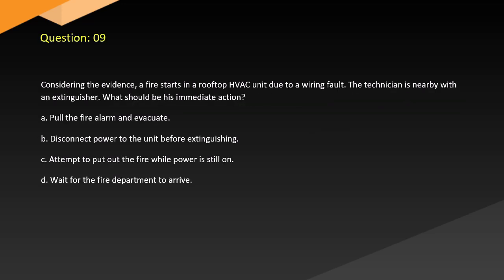Question 9. Considering the evidence, a fire starts in a rooftop HVAC unit due to a wiring fault, and the technician is nearby with an extinguisher. What should be his immediate action? A. Pull the fire alarm and evacuate. B. Disconnect power to the unit before extinguishing. C. Attempt to put out the fire while power is still on. D. Wait for the fire department to arrive.